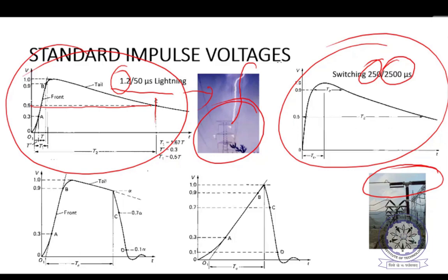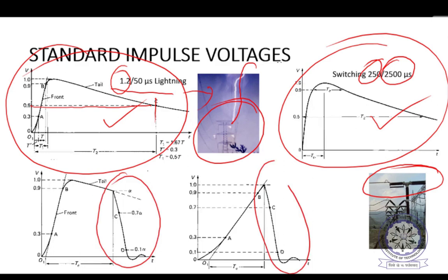So these 2 are standard lightning and this is standard impulse, standard switching waveforms. Apart from these, sometimes the breakdown or flashover may occur somewhere in either the tail or the front, and the wave is chopped off. So this is how the actual waveform may be chopped off. This is in front and this is here in the tail side. So the waveform depends on where exactly it gets chopped off due to flashover or breakdown or whatever.